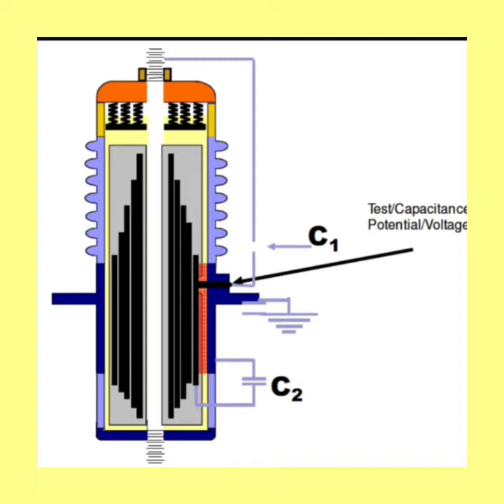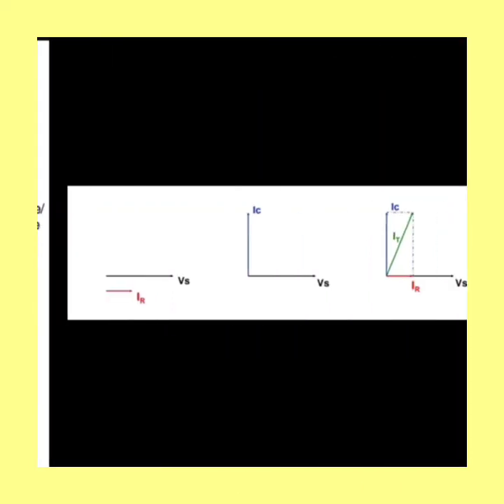Insulator is like a capacitor, and in a capacitor it is a known fact that the voltage lags the current by 90 degrees, and for the resistive load both are in phase. But no insulator can be a perfect insulator. The current is not leading the voltage by 90 degrees exactly because of some leakage current in the insulator as shown in the picture here.